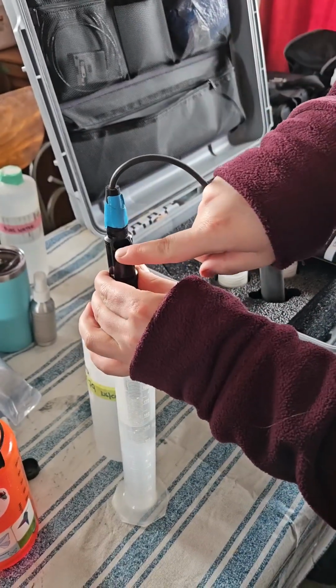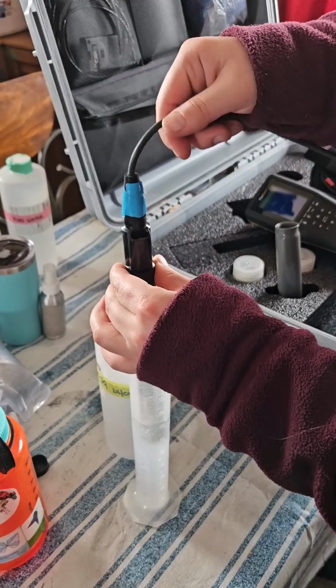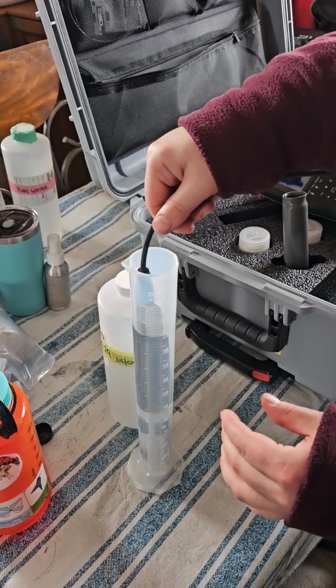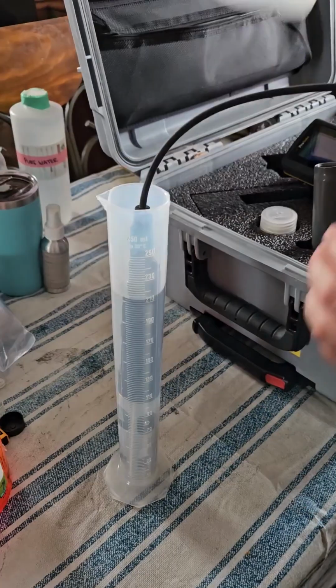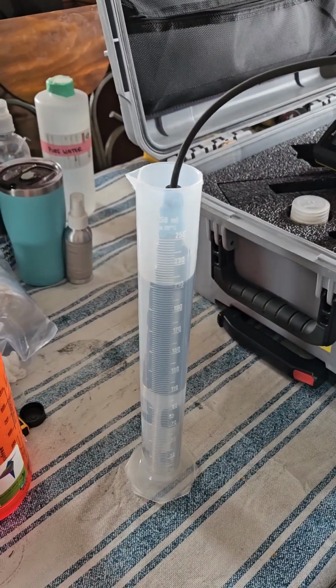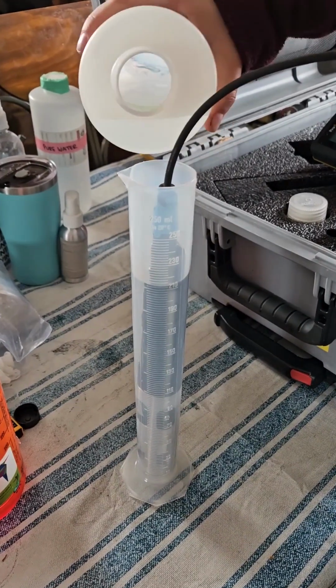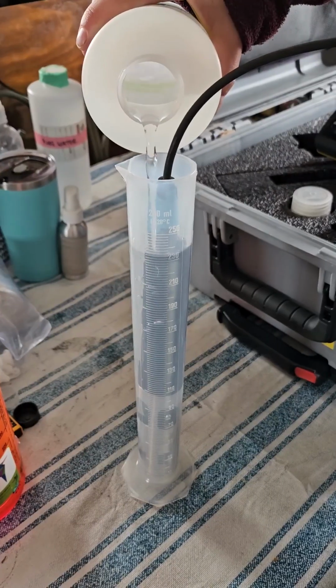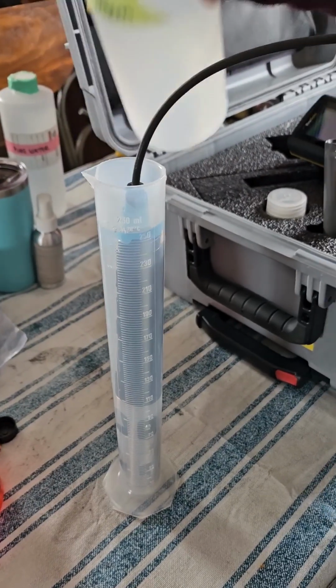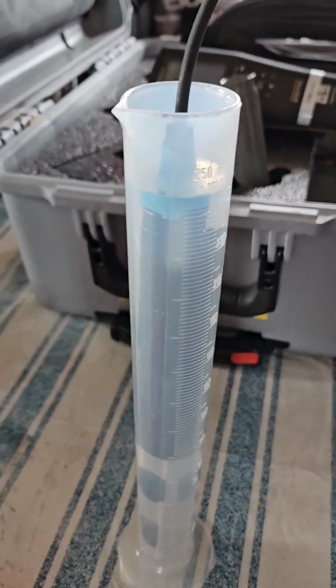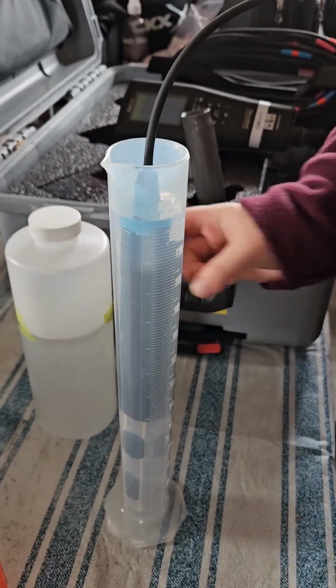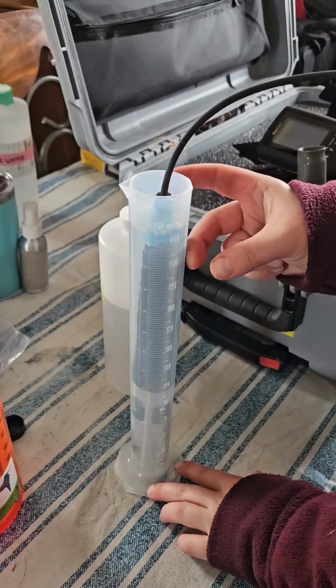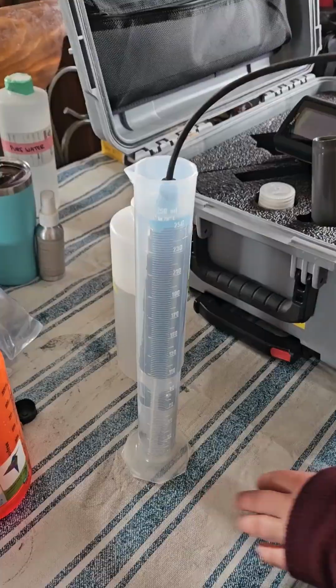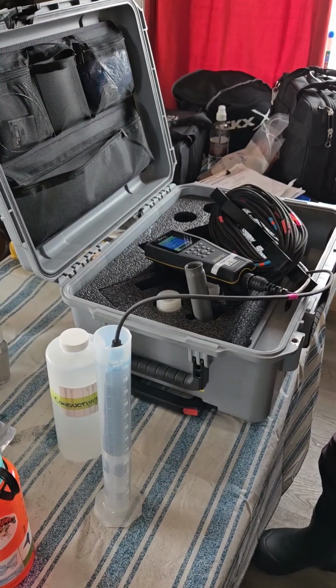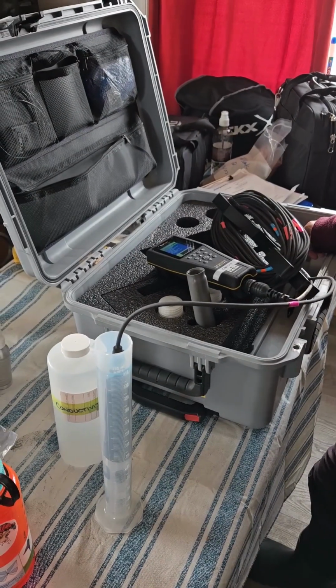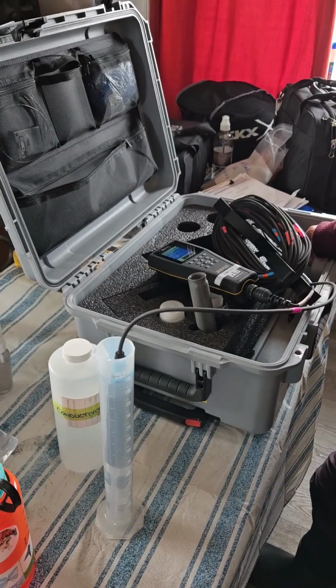And so we see here, this is the calibration sensor. We want to make sure that that is completely submerged in the calibration solution. So when you put it in, if it's not completely full, we'll just top it up so that that sensor is covered. And we'll flick it so that if there's any air bubbles that they will escape. We will let this sit for about a minute to acclimate to the solution.